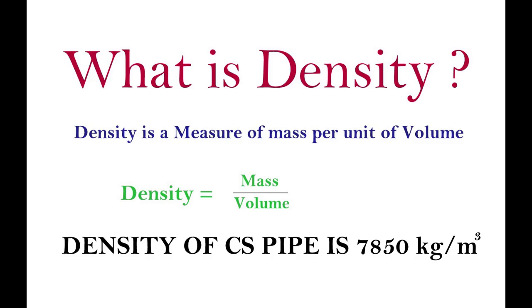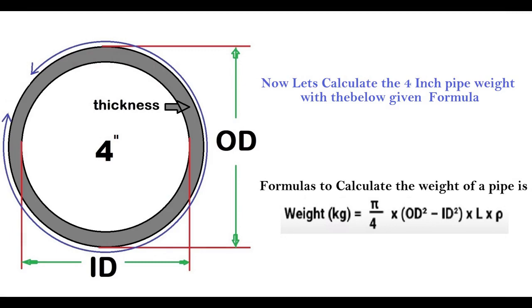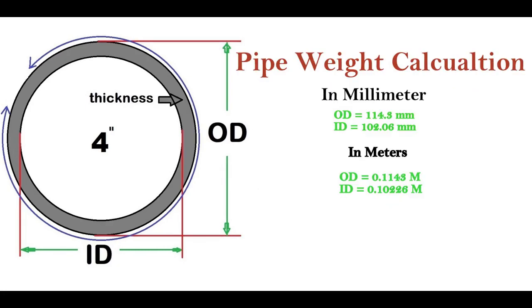So now let's calculate the four inch pipe weight with the help of the formula given below. The formula to calculate weight is equal to π/4 × (OD² - ID²) × length of pipe × density. Here, length of pipe we will take as 1 meter.